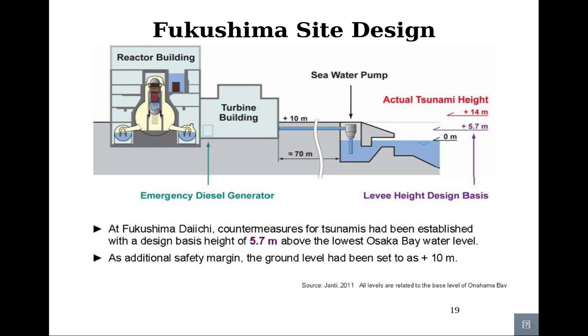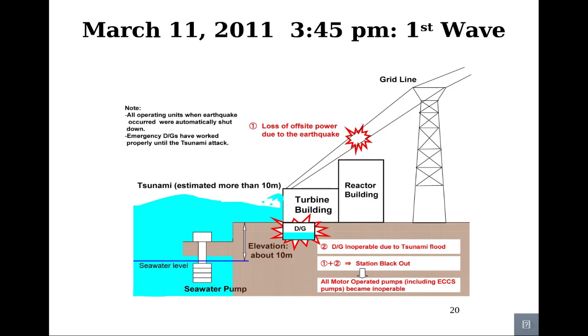This slide illustrates Fukushima Unit 1's design basis. As we can see, this particular tsunami exceeded design basis by at least a factor of 2. Losing off-site power might have been foreseeable in such an accident, since the majority of the components are not safety related. However, losing emergency diesel generator power, which supplied most of the instrumentation of the core and the ability to vent and add water to the core, would lead the station on a path of peril.